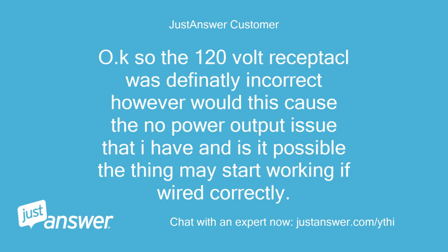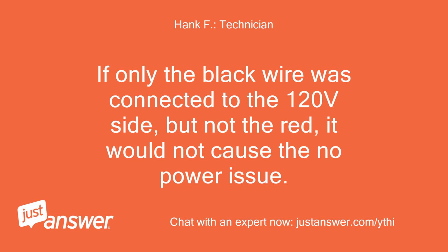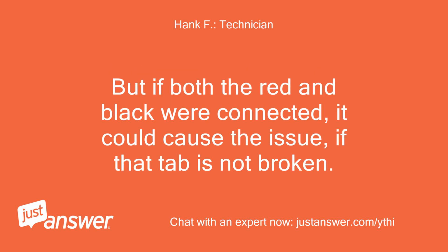Okay, so the 120-volt receptacle was definitely incorrect. However, would this cause the no power output issue that I have, and is it possible the thing may start working if wired correctly? If only the black wire was connected to the 120-volt side, but not the red, it would not cause the no power issue. But if both the red and black were connected, it could cause the issue, if that tab is not broken.